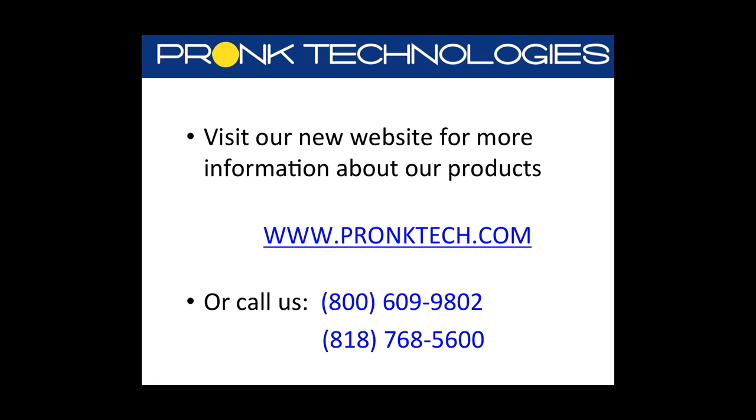Thank you so much, Greg. We have a bunch of questions. Question one: who is a good resource to contact if I need help doing accuracy or uncertainty calculations between the medical device and test equipment? Start with your calibration lab, as they're able to untangle different specifications and how they relate better than most. You can also go back to the test equipment vendor. Question two: does the Flowtrax infusion pump tester give you a 4-to-1 ratio for volume and occlusion testing? Yes, it does — it took a long time to get there, but we were able to achieve that 4-to-1 relationship. Some other questions submitted were lengthy and technical, so those have been forwarded to Pronk and their representatives will be replying directly.